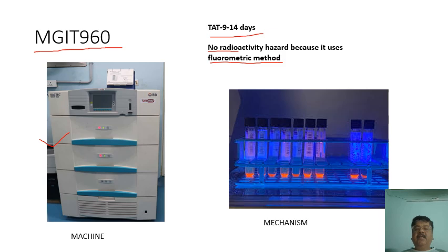In this, because of the metabolic activity of the growing organism, the oxygen is absorbed. Lack of oxygen in the medium will cause fluorescence in the medium, from the fluorogenic substance, which is detected by the sensors. So the presence of oxygen will quench the fluorescence.